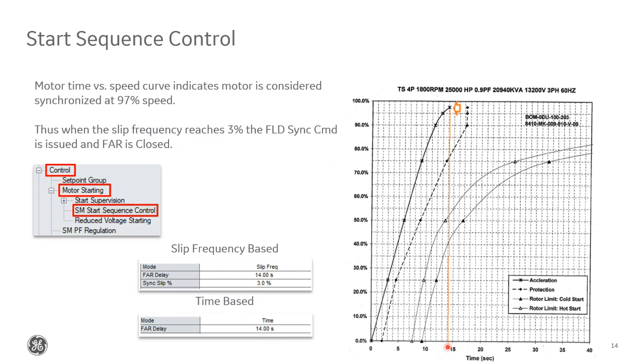Now, a key thing to note here is that the slip frequency mode is only applicable to brush type motors, since we need to be able to measure the speed to calculate the slip, which can only be done if we have a measurement of the voltage of the actual field winding. In the case of the brushless motor, which we saw a minute ago, which has the excitation system mounted directly on the rotor and is rotating, we don't have that measurement available. And this is pretty typical of most synchronous motor controllers. If you don't have that measurement, then you simply choose time-based and set it based on your data sheet.